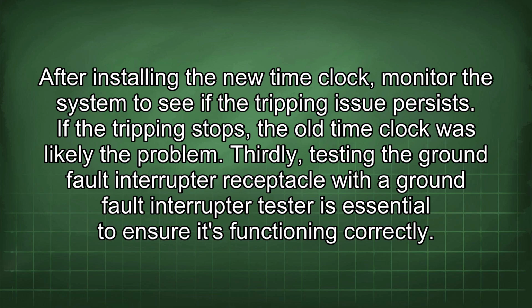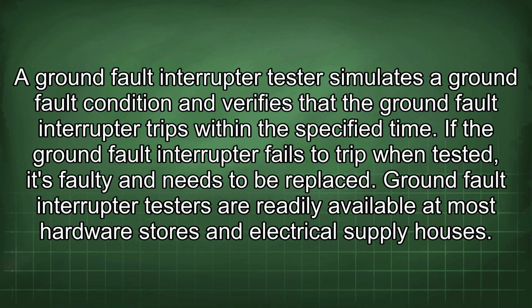Thirdly, testing the ground fault interrupter receptacle with a ground fault interrupter tester is essential to ensure it's functioning correctly. A ground fault interrupter tester simulates a ground fault condition and verifies that the ground fault interrupter trips within the specified time. If the ground fault interrupter fails to trip when tested, it's faulty and needs to be replaced. Ground fault interrupter testers are readily available at most hardware stores and electrical supply houses.